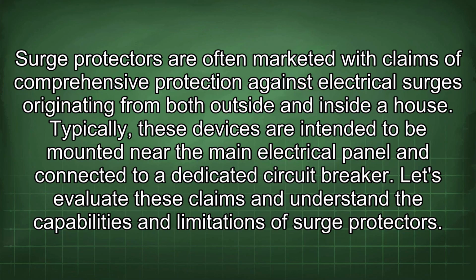Surge protectors are often marketed with claims of comprehensive protection against electrical surges originating from both outside and inside a house. Typically, these devices are intended to be mounted near the main electrical panel and connected to a dedicated circuit breaker. Let's evaluate these claims and understand the capabilities and limitations of surge protectors.